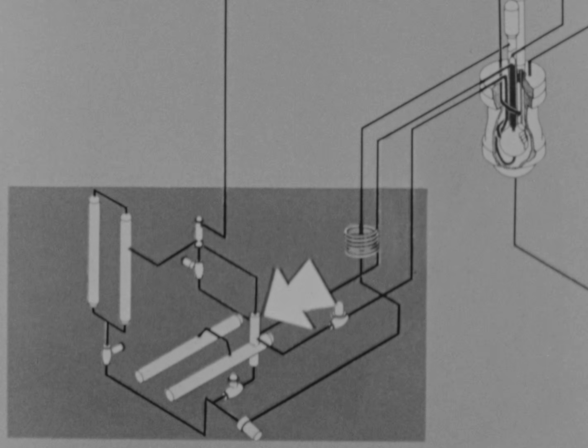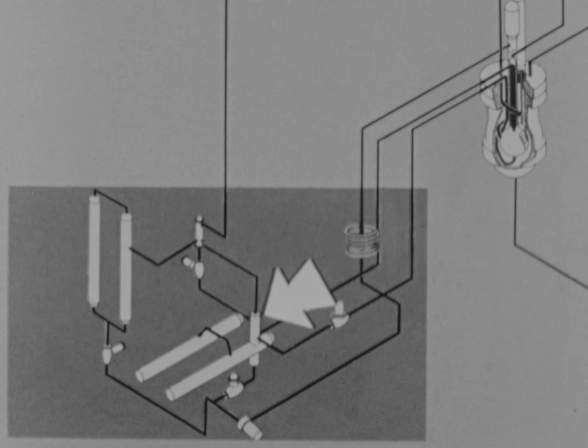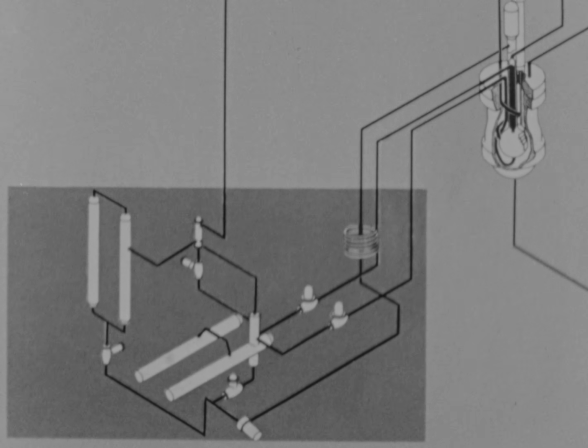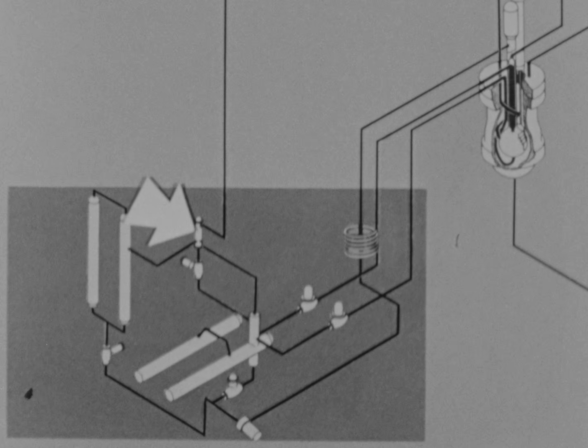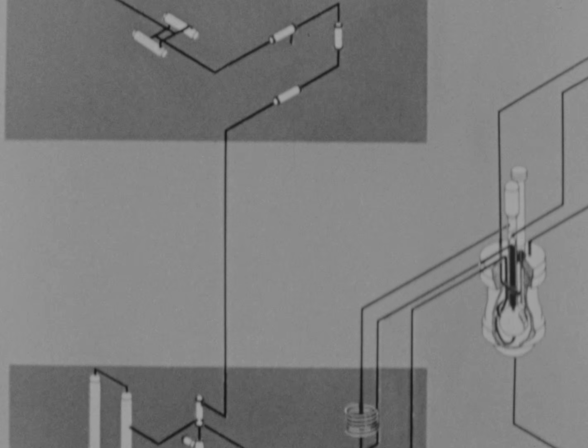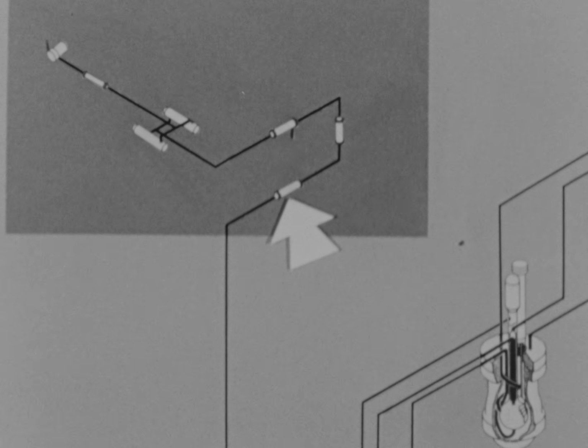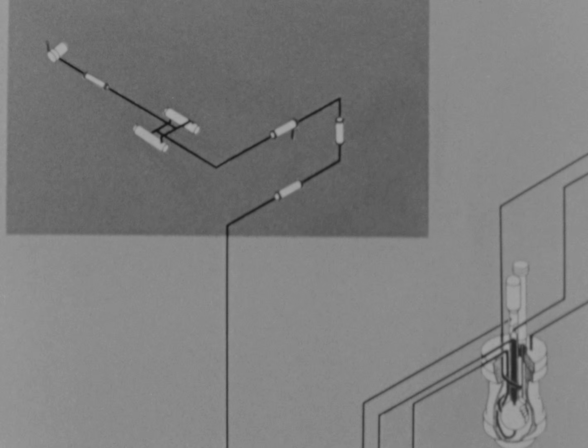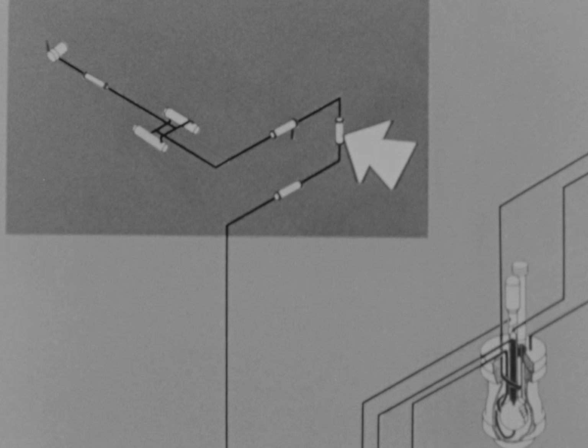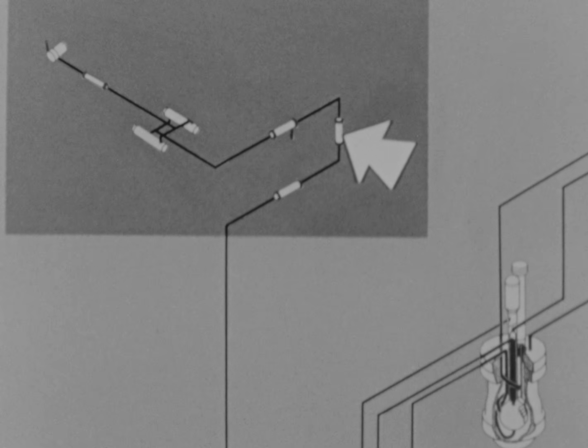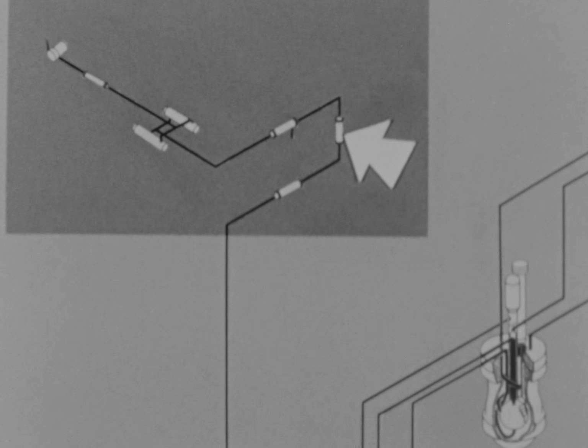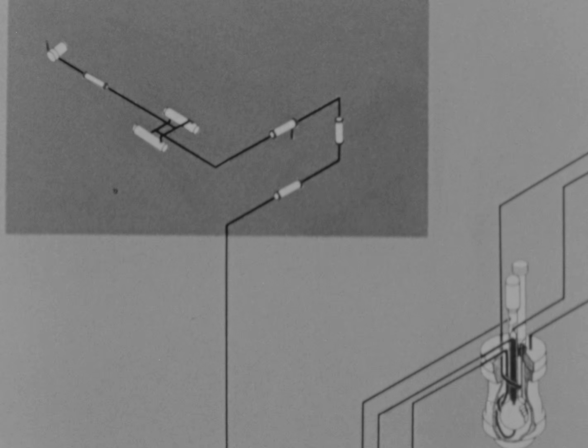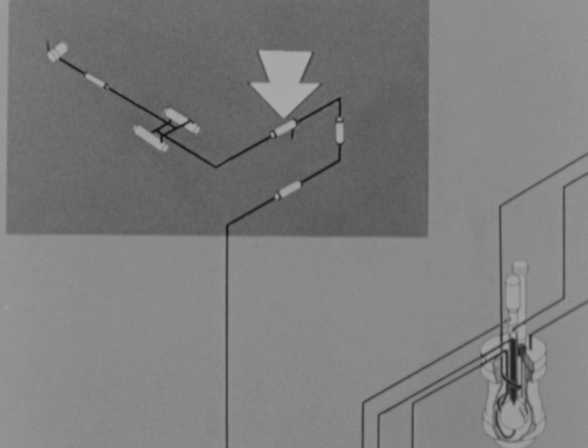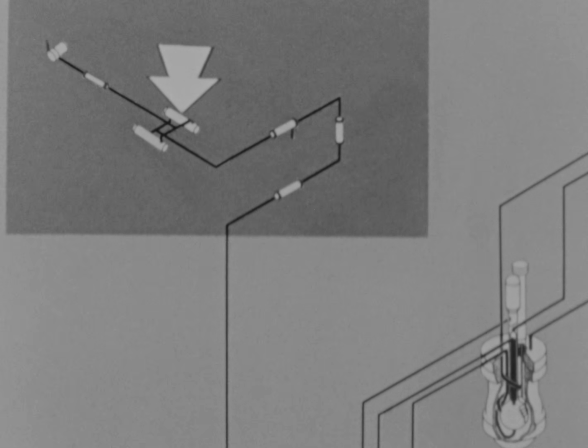A small evaporator generated steam to dilute the gases. The steam and gases rose to a condenser where water vapor was removed, and to a flame recombiner where the hydrogen and oxygen were burned to form water. A small catalytic recombiner accomplished this recombination during low-power operation when the gas flow was insufficient to maintain a flame. Another condenser followed the recombiners to remove heat and recombined water. Cold traps removed remaining traces of water.